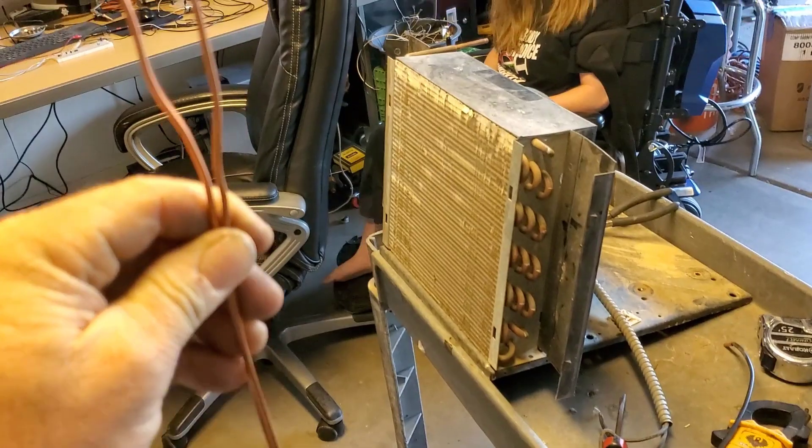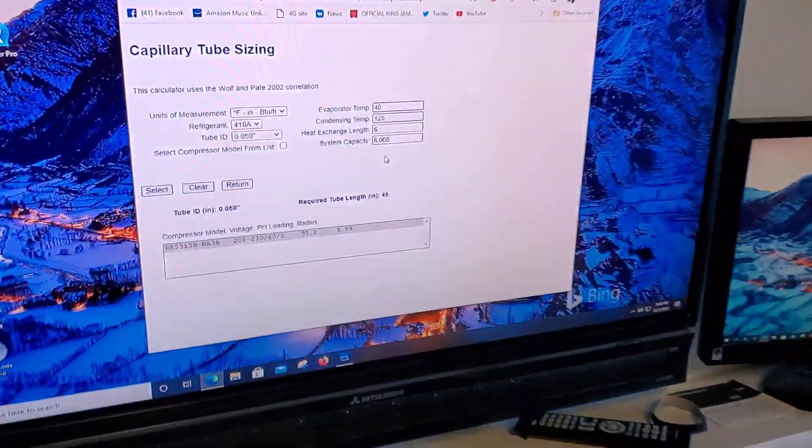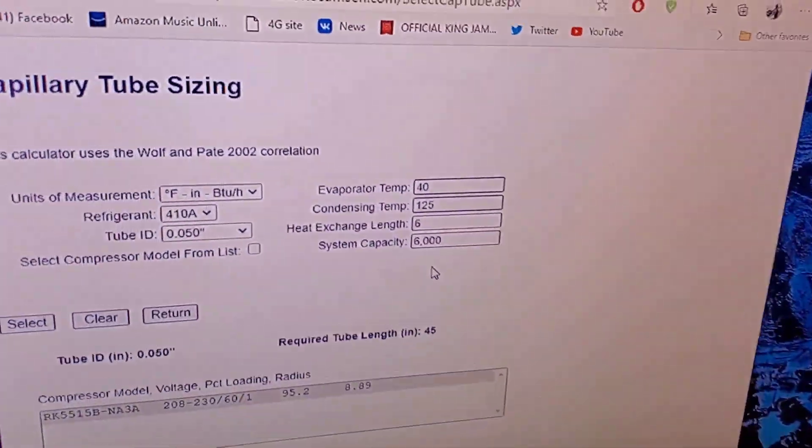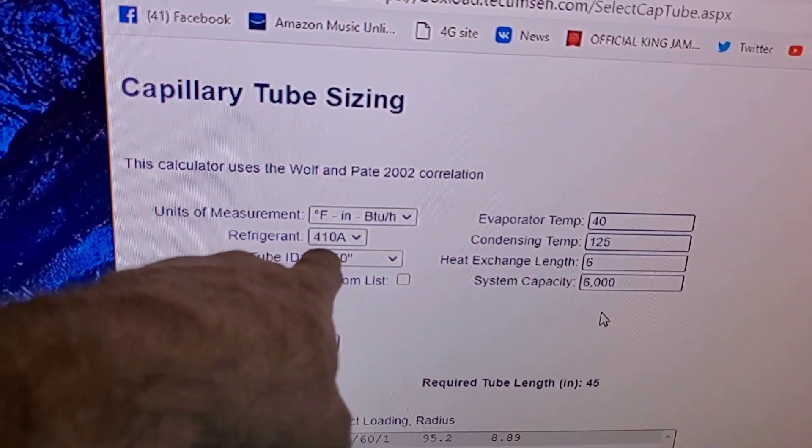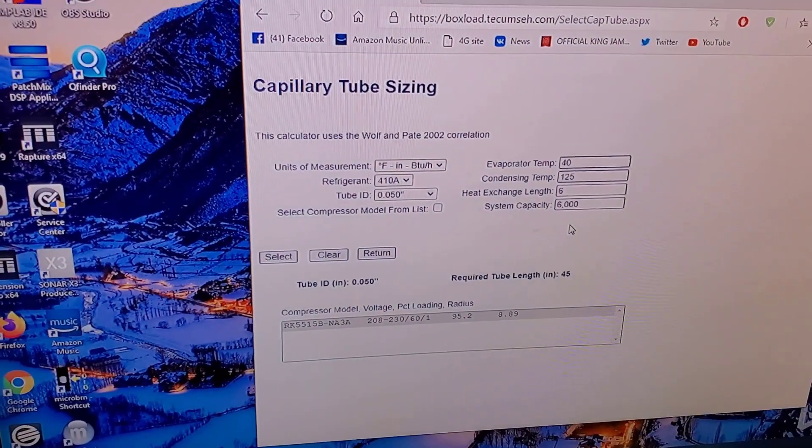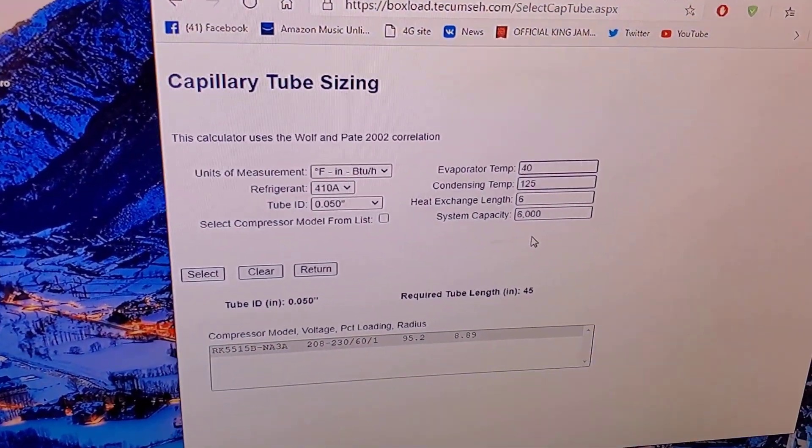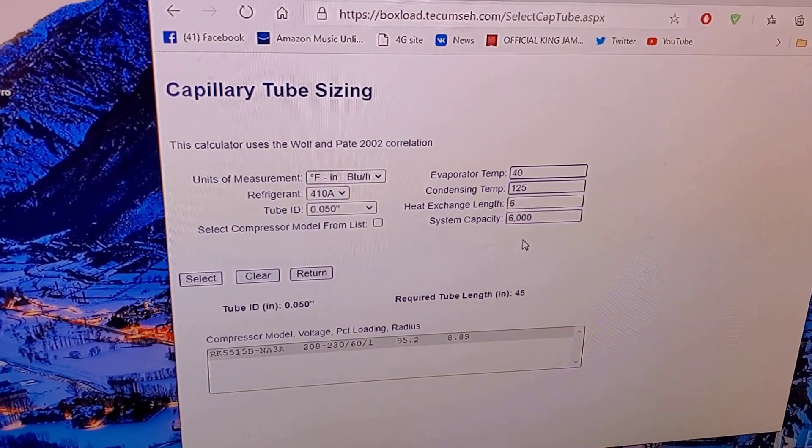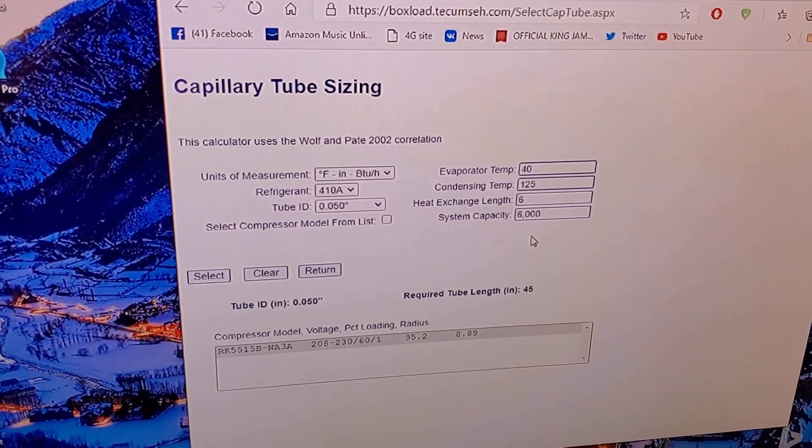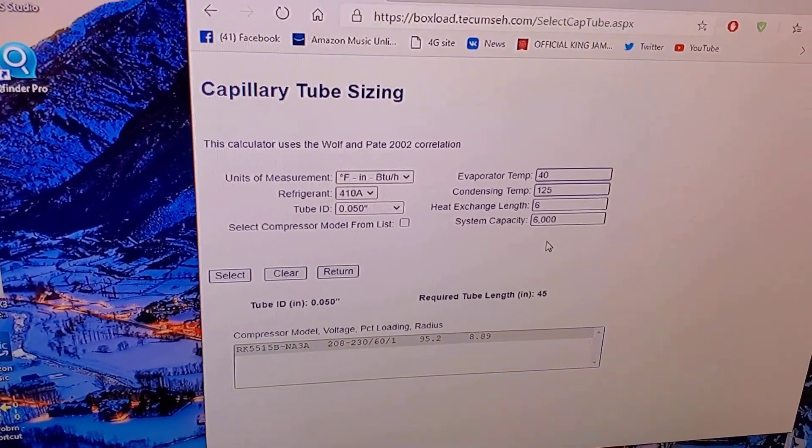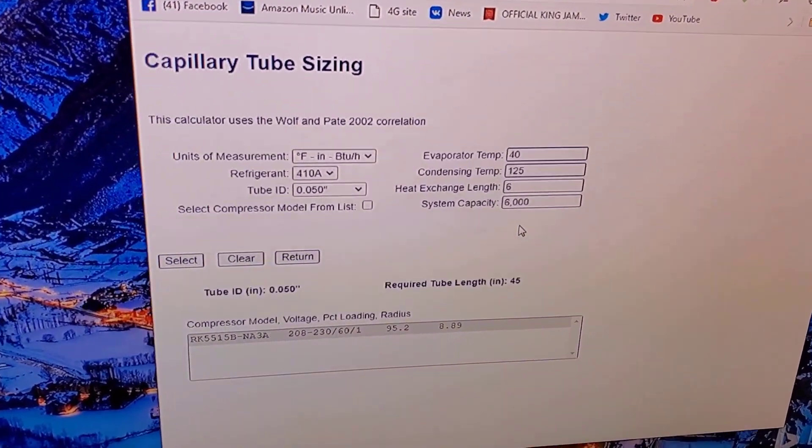Okay, I just cut myself two capillary tubes. I found an online calculator, put refrigerant 410A in there, threw in some arbitrary numbers—40 degree evaporator and 6,000 BTUs apiece, so 12,000 total but half and half. Hopefully that gives me the right length. It spit out 45 inches.